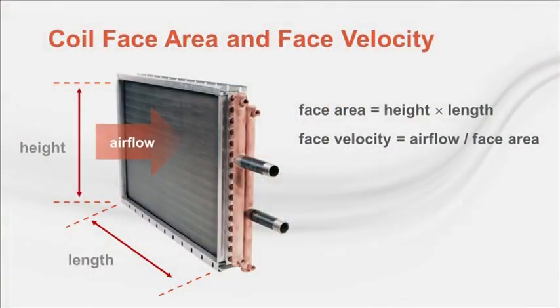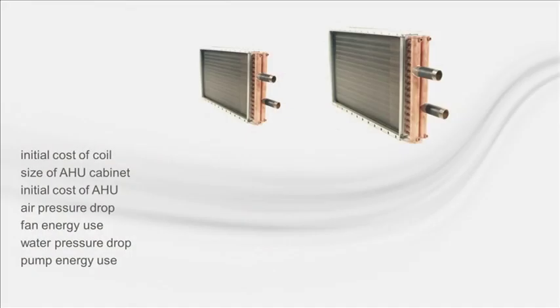The effects of these design choices become more apparent when looking at actual coil selections. For chilled water coils, the cooling coil must be selected to prevent moisture carryover. The face area of the coil dictates the size of the air handler cabinet. The selection of the chilled water coil impacts the cost of installing and maintaining both the air handling unit and the chilled water system. The amount of material used to construct the coil determines its initial cost, impacted by face area, number of tubes, and number of fins. A larger face area typically increases the cost of the coil itself.